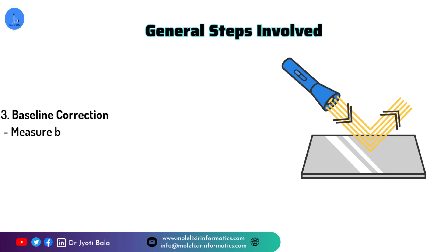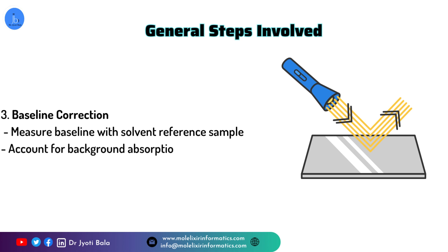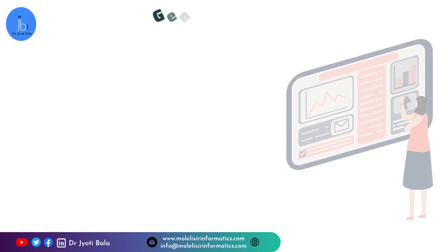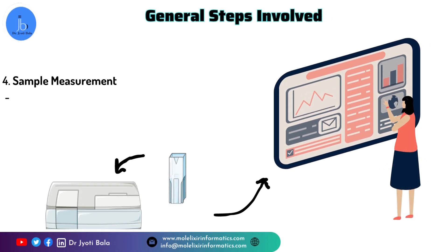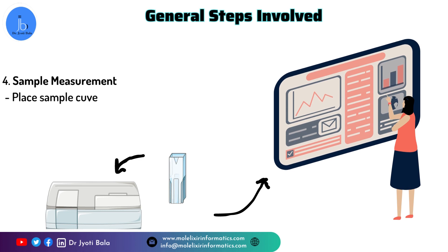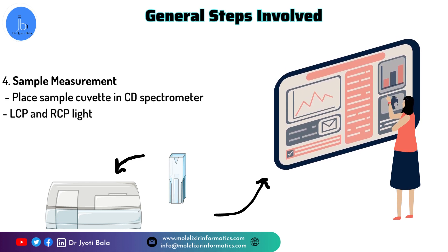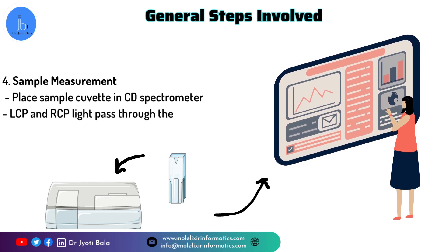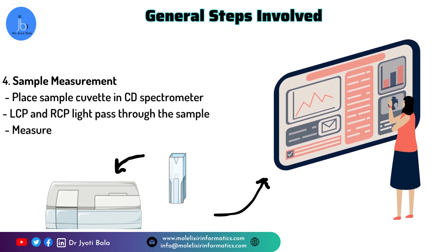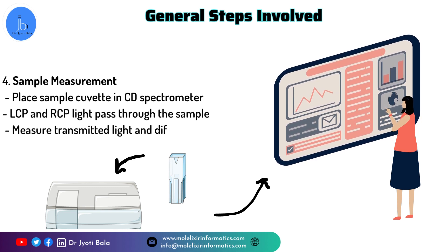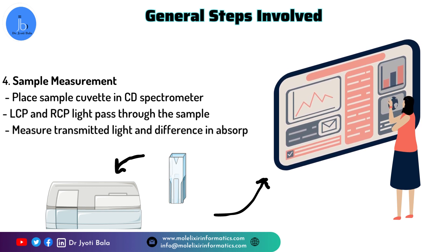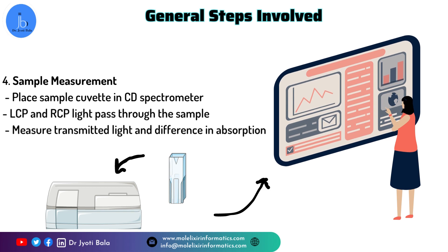Next, you also have to work on the baseline correction. A baseline measurement is performed with a solvent reference sample to account for any background absorption or instrument noise, and later on you can do the sample measurement. Usually, the sample cuvette which contains the dissolved molecule is placed in the CD spectrophotometer. The spectrophotometer emits both LCP and RCP light which passes through the sample. The transmitted light is detected and the difference in the absorption between LCP and RCP is measured.